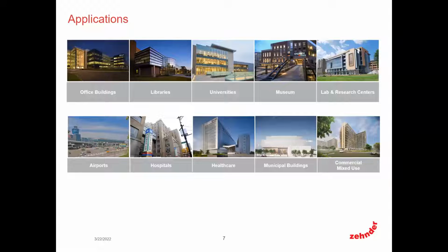I would say a lot of the airports throughout North America are now utilizing the radiant cooling and heating system. Even if that airport is not utilizing the cooling and heating within, say, the boarding areas or the interior core past the security, a lot of the airports are now using just the perimeter and using panels along that large glass facade to deal with that load. So healthcare is another popular application for us in the vertical market. I've seen hospitals, I've also seen laboratories themselves, and a lot of municipal buildings too.